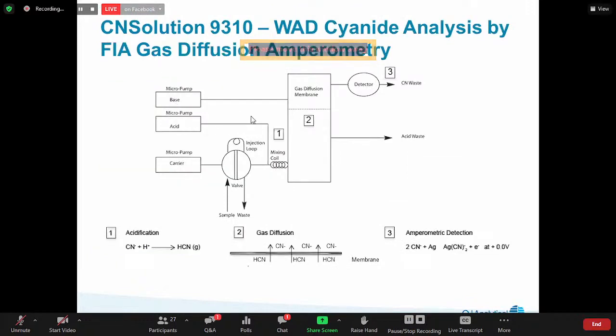So again, we've seen this schematic before. It's exactly like the one that we saw in the previous slides as far as the flow path goes for this instrumentation. And this is a more detailed look at how the CN9310 works. Very quickly, this valve will rotate to whichever port is called out in the sequence of what we want to measure, whether that be the low calibration standard, the high calibration standard, or one of the sample ports. When that is selected, this pump turns on and fills the sample loop with the representative sample.